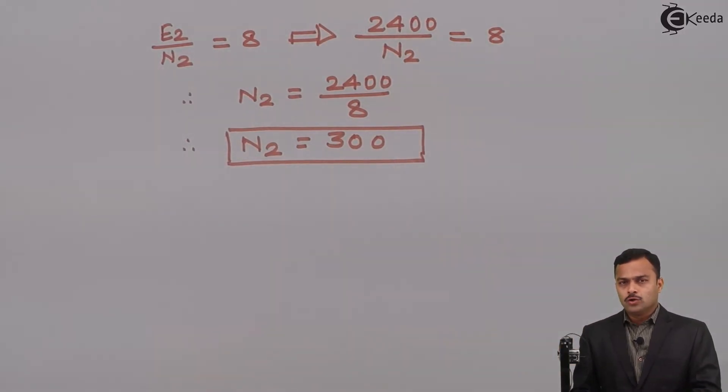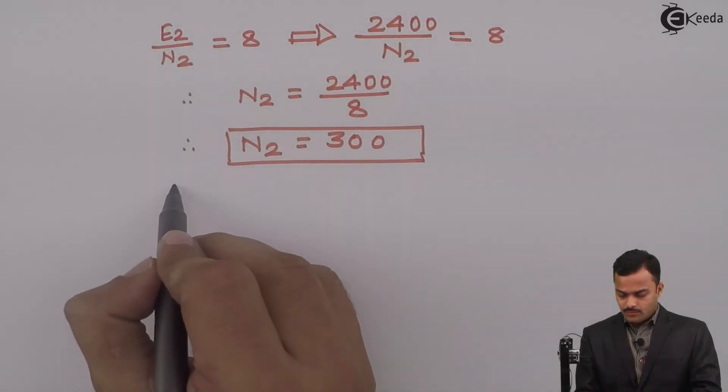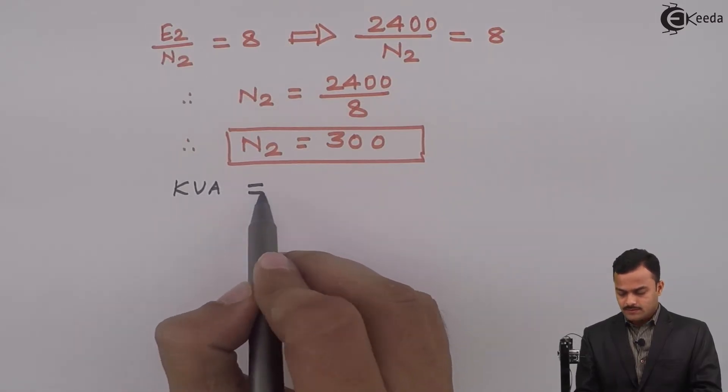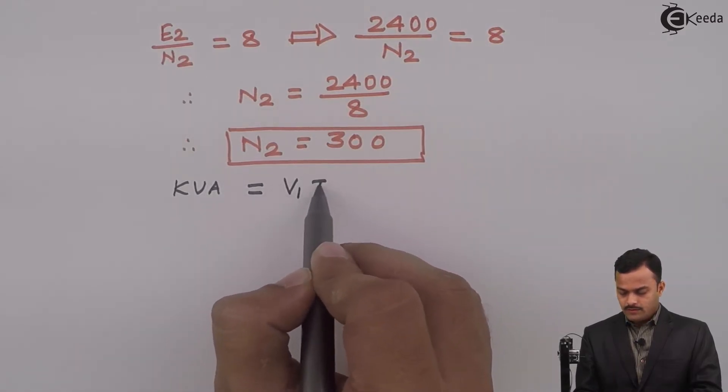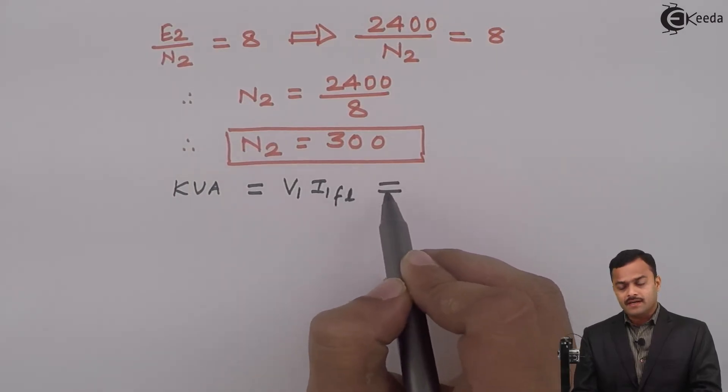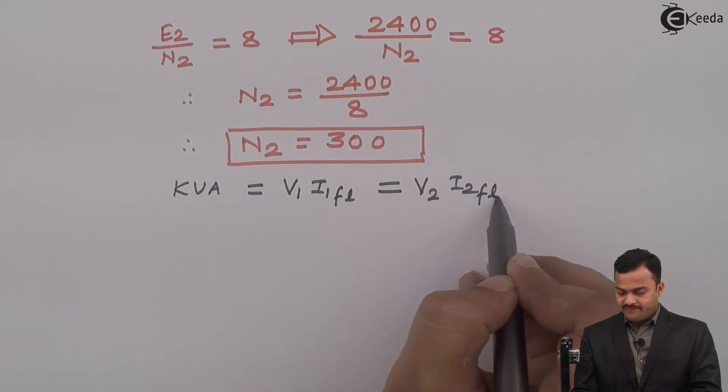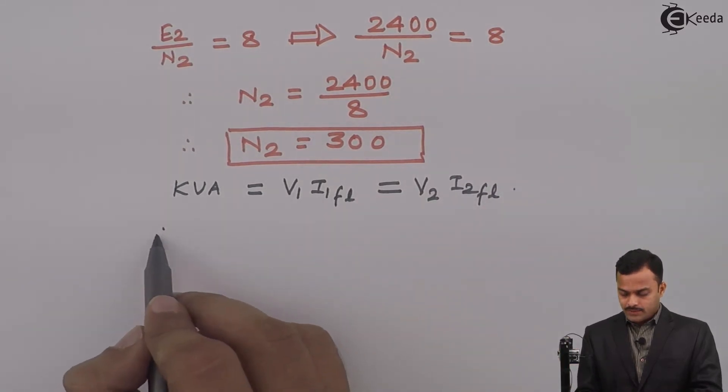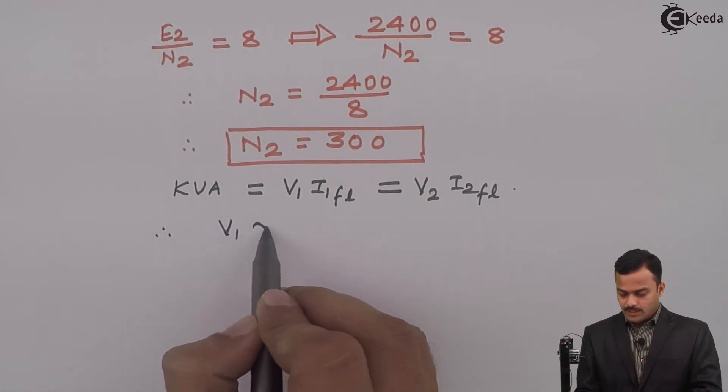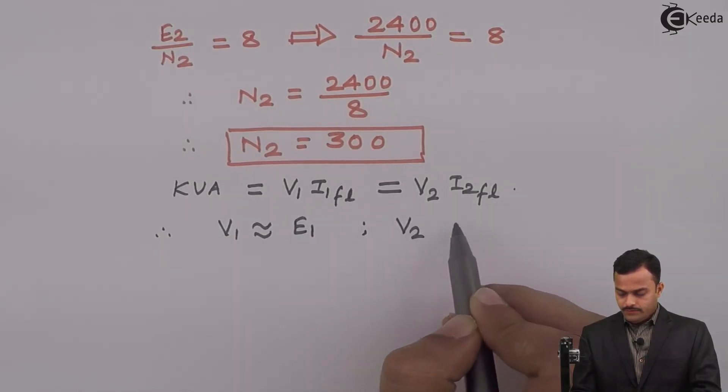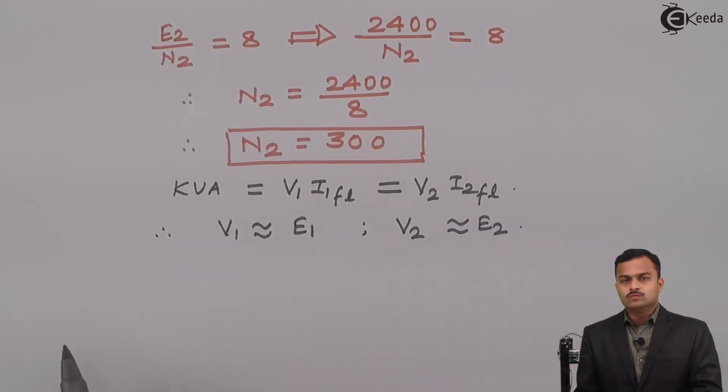Now, we have to get full load currents. For that I will use a simple formula: KVA rating of a transformer is nothing but V1 I1 FL which is same as V2 I2 FL and we approximate V1 as E1 and V2 as E2.